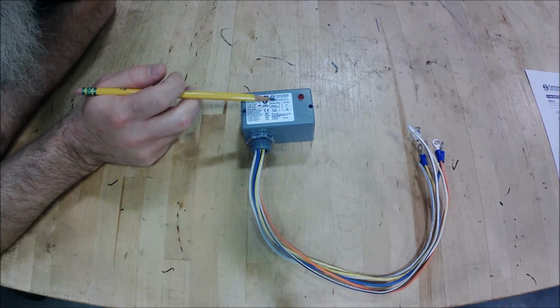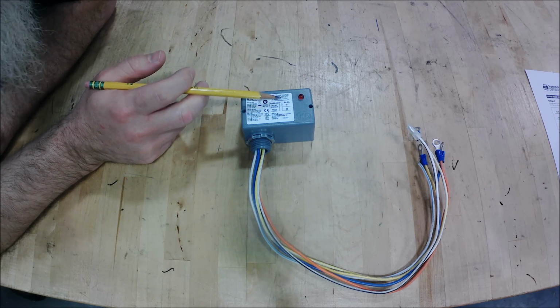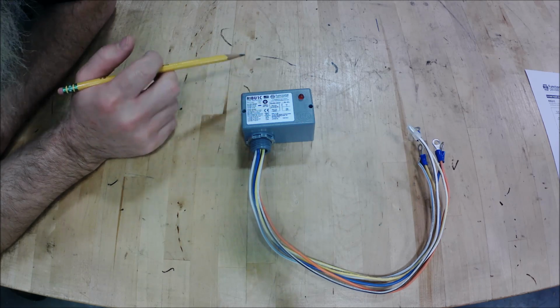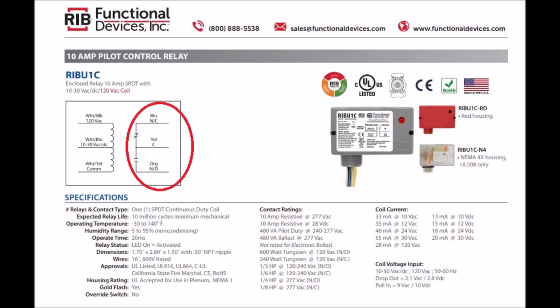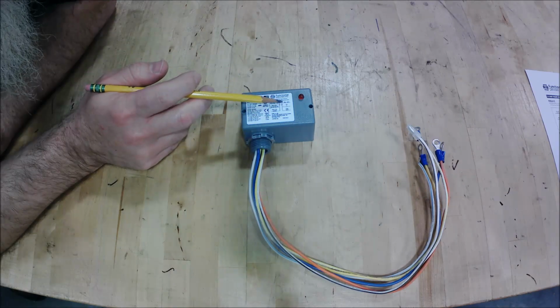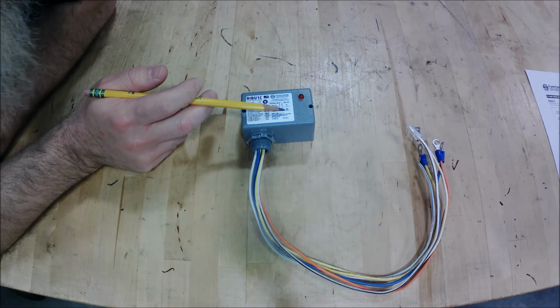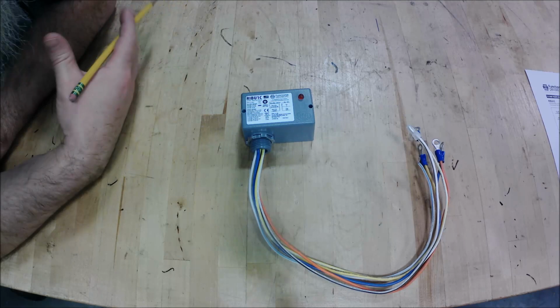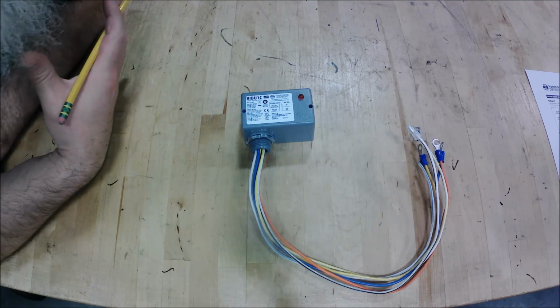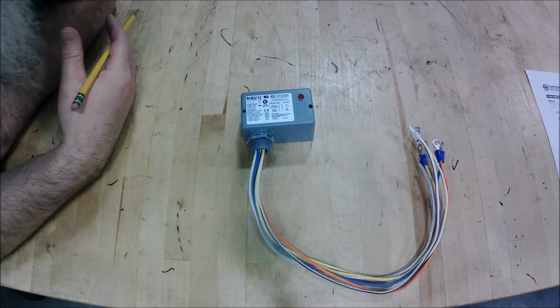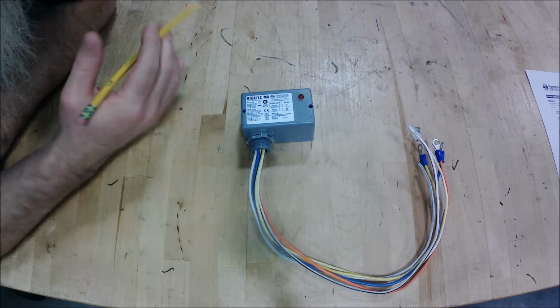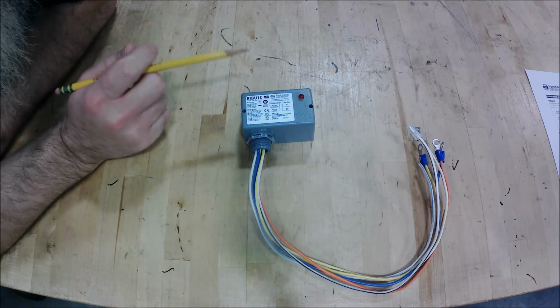So coil voltage on this side, and if you look on the other side, there's going to be your switches. You've got a normally closed, a common, and a normally open, and this looks exactly like a Goodman fan board. It looks exactly like a 9340 relay. Like I said, it's too simple.